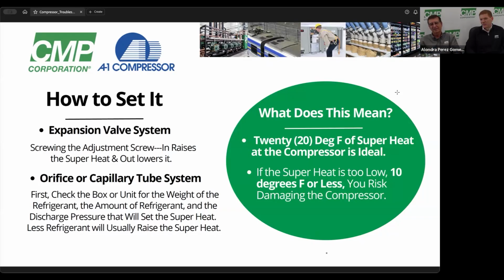Yes, sir. And like I said, 20 degrees superheat is pretty much ideal for what most compressor manufacturers want to see. Unless you have a chiller that sometimes has a very, very short suction line, where you're going to have to go with expansion valve superheat, which is going to be right around 10 to 12 degrees. But any superheat is better than no superheat, because if liquid enters the compressor, sooner or later you're going to be changing the compressor.